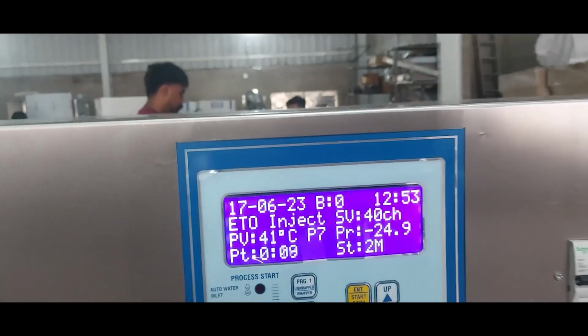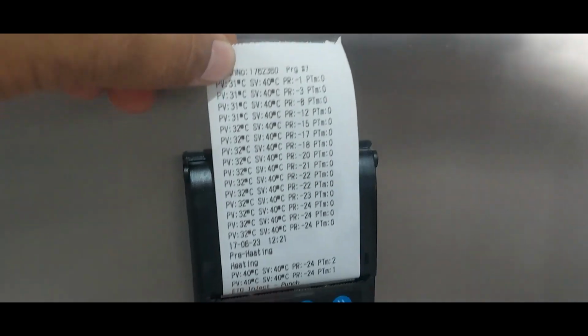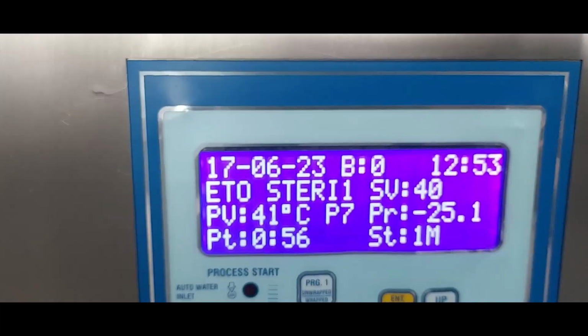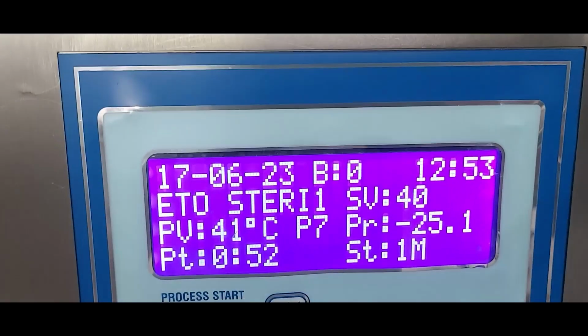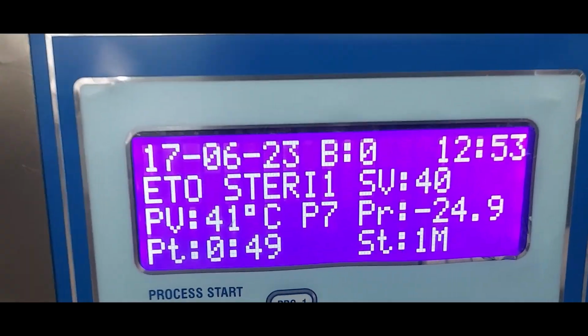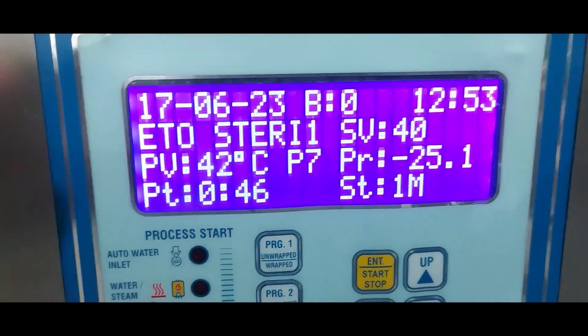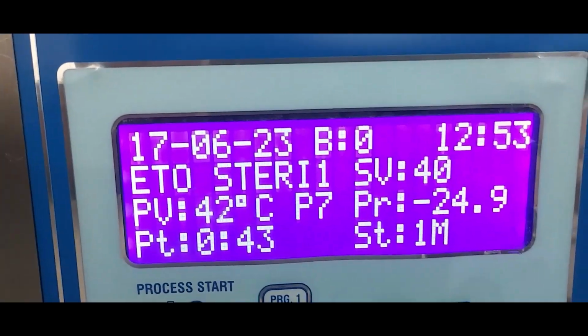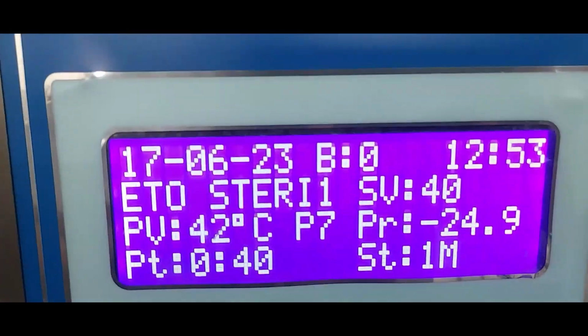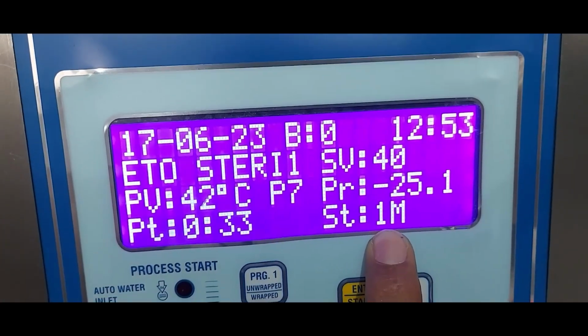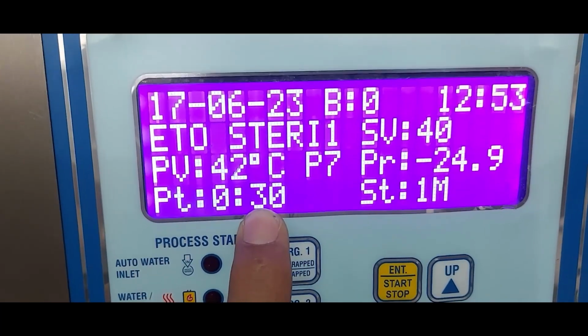The ETO sterilizer cycle is a continuous process. Here we see the cycle temperatures, preheating. Now the ETO sterilizer starts. For testing purposes, we put the ETO sterilizer time at only 1 minute. Once the ETO sterilizer time is over, because this is a test program we run for demo purposes, it will run the ETO sterilizer for the set time. Normally the time is 6 to 8 hours, depending on the material. And once the time is over, the ETO sterilizer will go into the second mode.